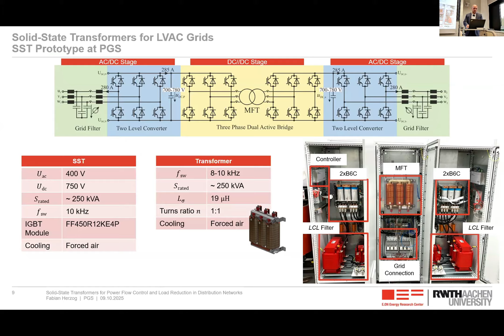So this is a 250 kVA medium frequency transformer for low voltage. And this is quite small. It's only 50 kilograms, it's switching at 10 kilohertz, and so we have 200 grams per kVA. As a comparison, I looked up one 250 kVA 50 hertz transformer. It weighs 710 kilograms, so much more, and we are at 2.84 kilograms per kVA. It's basically the same numbers as we saw in the previous picture. We can also see here at the bottom the LCL filters, which are also quite large in this solid state transformer. Here are the specifications. The DC link voltage is 750 volts. We have around 250 kVA of power, as I said, and everything is cooled with air.